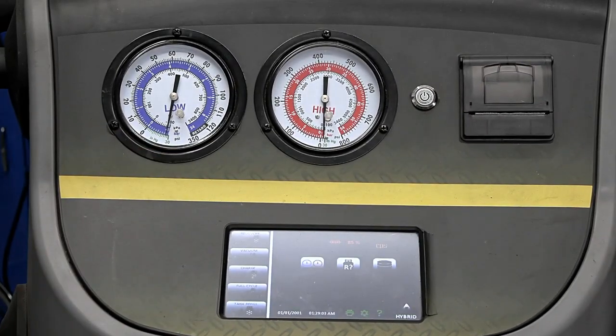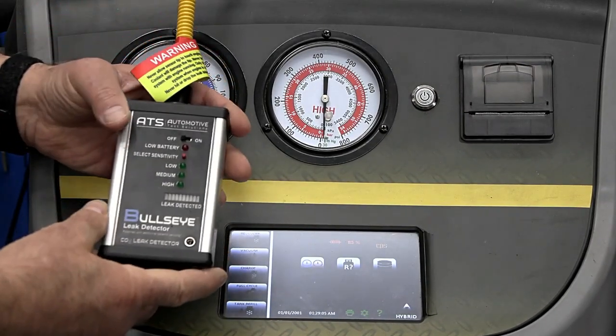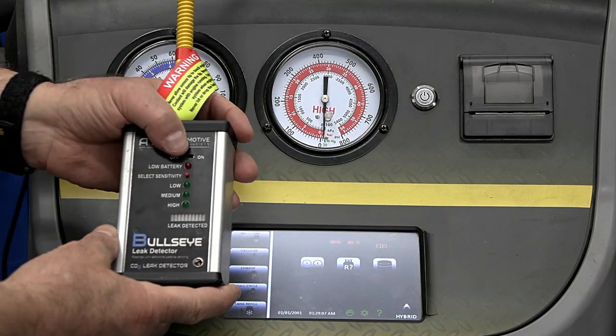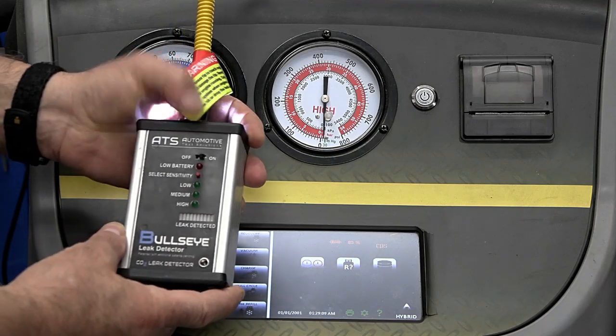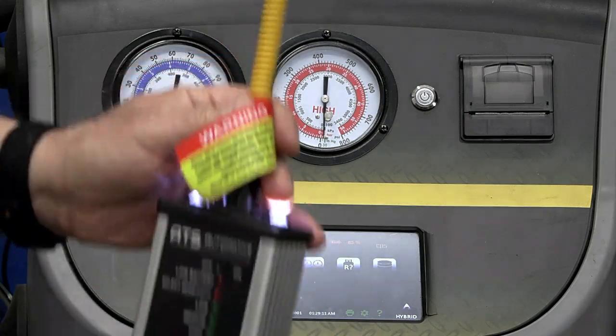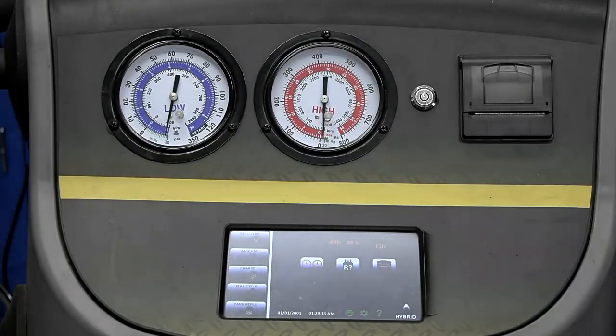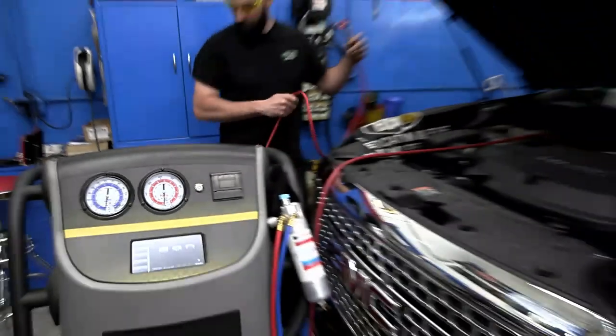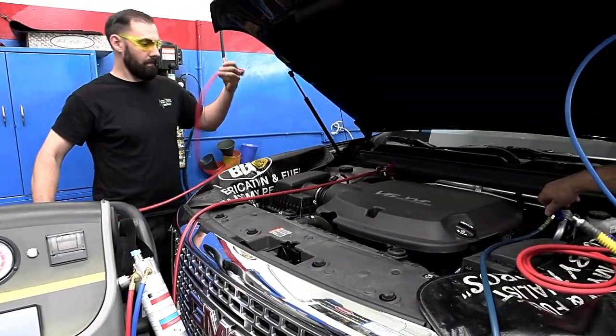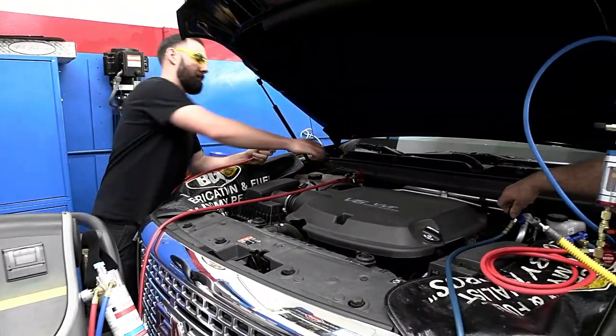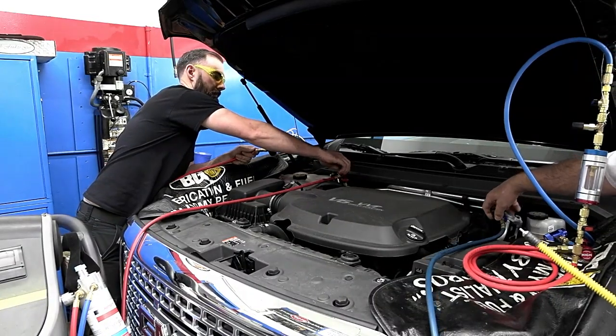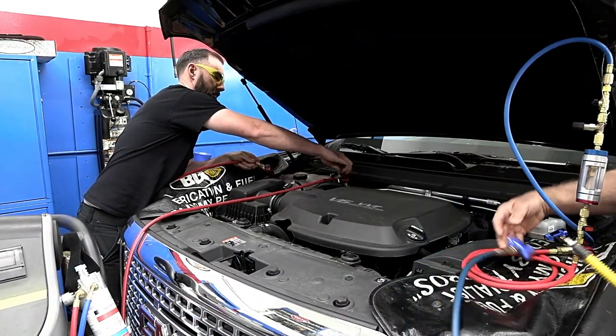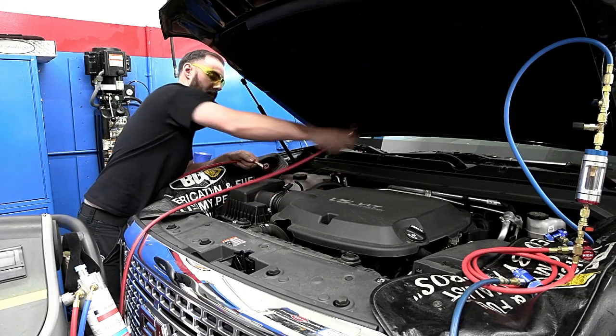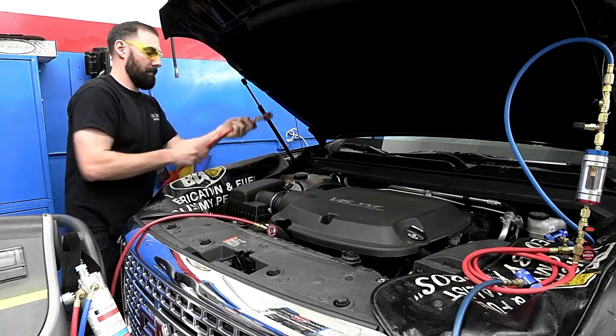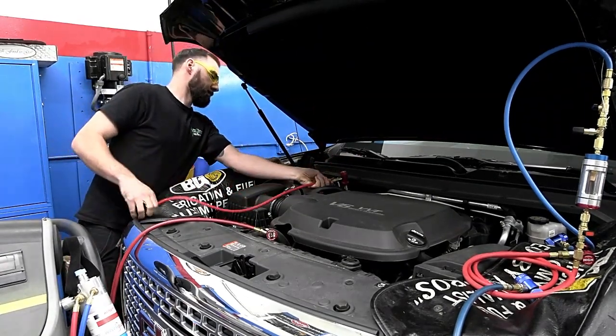Thank you, Franklin. We're going to use this thing here called Bullseye to find a CO2 leak. I'm going to put it on and let it warm up. Bill's going to put that there — he's going to go on the high side. I'm disconnecting this unit here, the low side, and Bill's going to disconnect the high side. What we're going to do is introduce 200 pounds of CO2. This will beep till it warms up and goes into a mode.